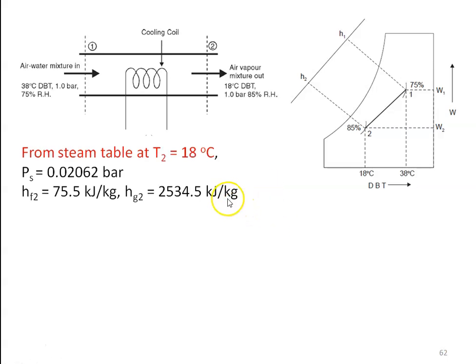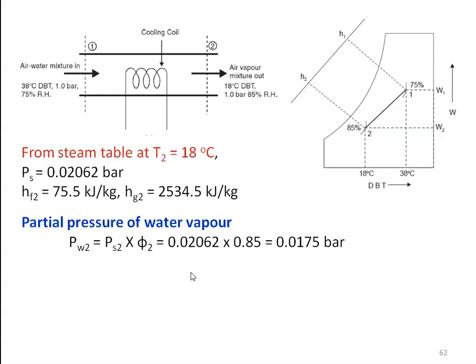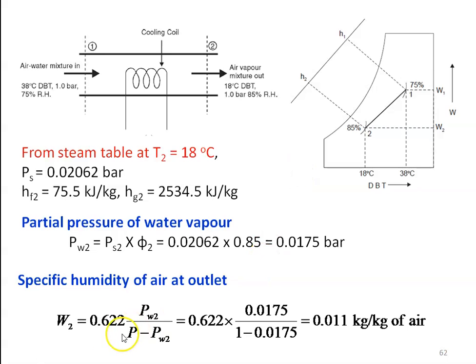Again from the steam table at T2 equal to 18 degree Celsius, the saturation pressure PS2 equal to 0.02062 bar, enthalpy of water HF2 equal to 75.5 kilojoules per kilogram, and enthalpy of vapor HG2 equal to 2534.5 kilojoules per kilogram. The partial pressure of water vapor PW2 equal to PS2 into φ2, which is 0.02062 into 0.85 equal to 0.0175 bar. The specific humidity at the outlet: W2 equal to 0.622 × 0.0175 divided by (1 minus 0.0175) equal to 0.011 kg per kg of air.